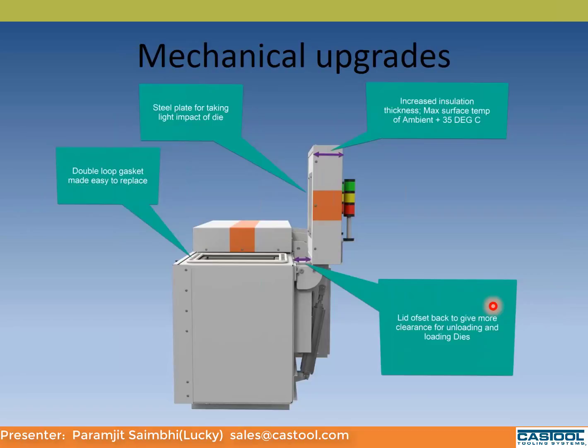These are the mechanical upgrades we have done. So, you have the lid, which is a lot thicker now. Obviously, all around our insulation is around 6 inches rather than 4 inches. You have a steel plate for the lid, so it takes an impact. Then you have your gasket, which is double looped, so it lasts longer. It gives you better sealing. And then the lid has been offset back a few inches as well, so you have more space for loading a die into the cell without hitting the lid.